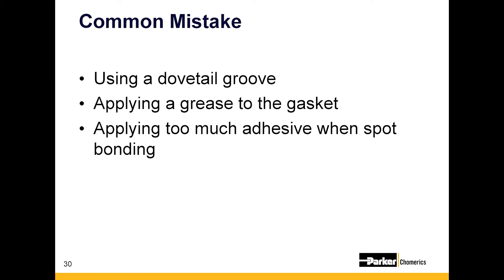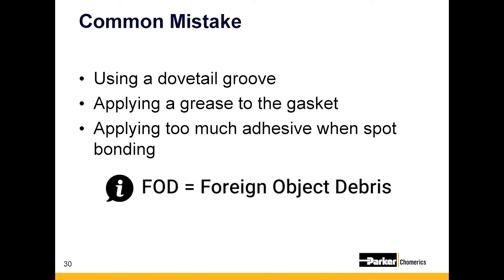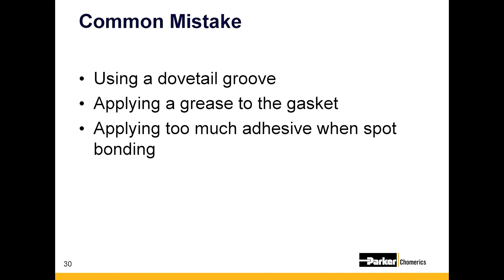One of the most important common mistakes is using a dovetail groove. Conductive elastomer gaskets should always be designed in compression — never in shear, tension, or rotation of any kind, due to FOD concerns. A gasket installed in a dovetail groove can shear on the way in or out. Additionally, elastomer gaskets need a minimum of three points of contact to create a ground or shield. An underfilled gasket in a dovetail groove may give you as little as one point of compression, which won't provide shielding, grounding, or water sealing.